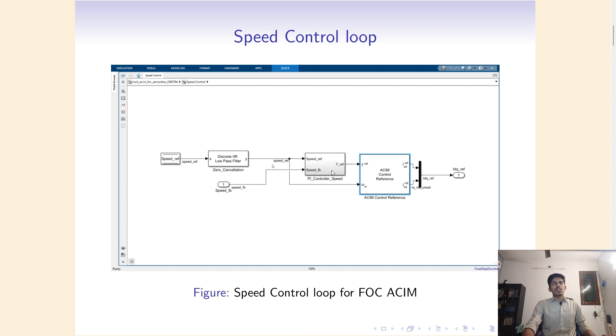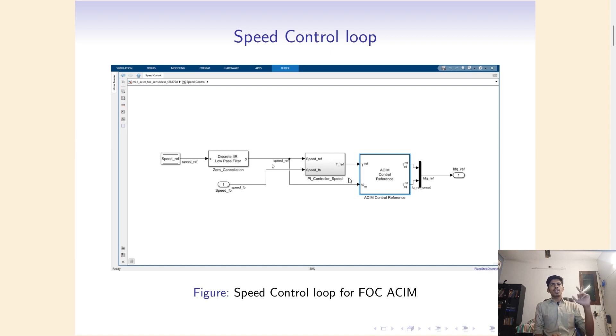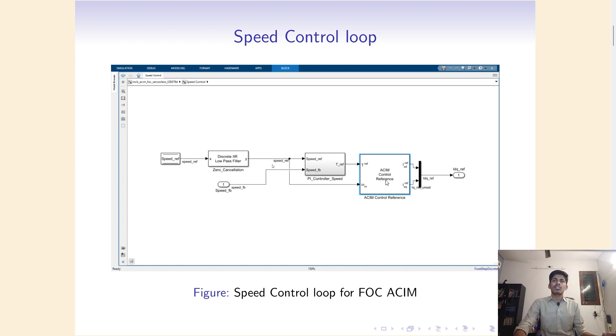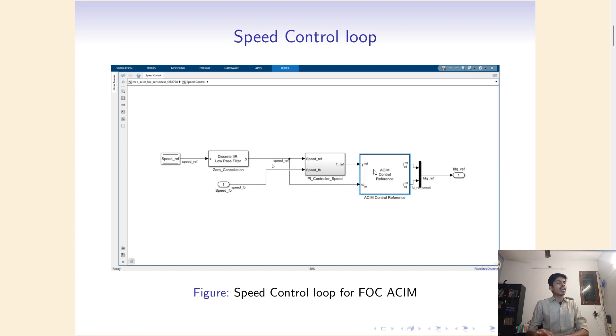Inside, we can see that the speed reference is passed to a PI controller and the actual speed of the motor is also passed, generating a torque reference. There is a PI controller taking the two speeds, generating an error, multiplying by the gain, and giving the torque reference. The speed reference and the torque reference are then given to an inbuilt block called the AC Induction Motor Control Reference block.